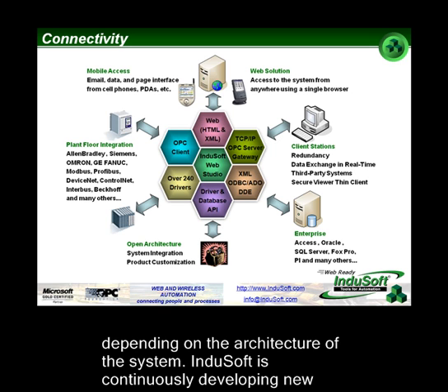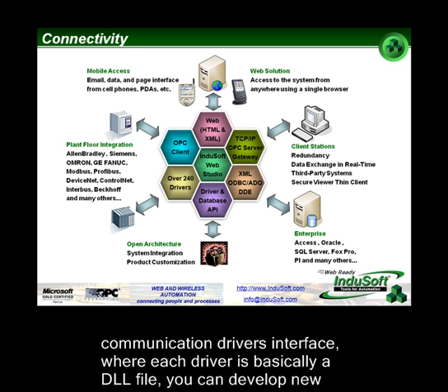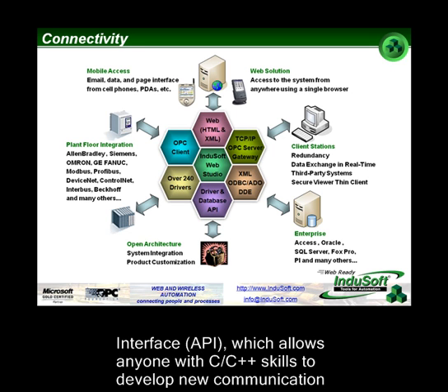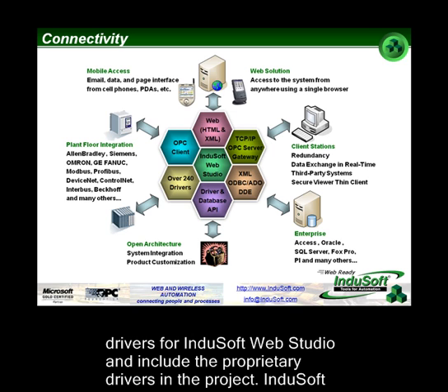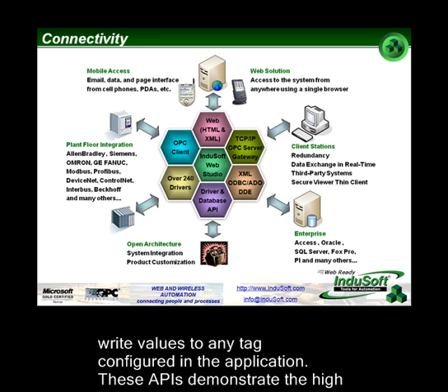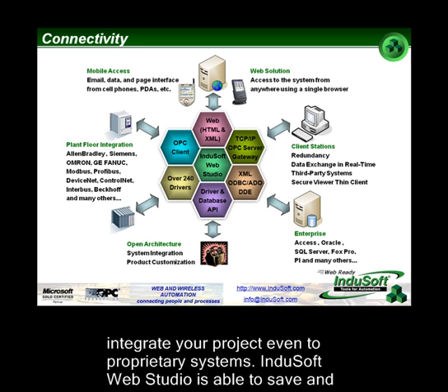InduSoft is continuously developing new communication drivers for emerging protocols. However, based on the modularity of the communication drivers interface — where each driver is basically a DLL file — you can develop new drivers yourself using the driver toolkit, an API that allows anyone with C or C++ skills to develop new communication drivers for InduSoft Web Studio. InduSoft also provides another API called the Tags Database Access Toolkit, which allows you to read or write values to any tag configured in the application. These APIs demonstrate the high level of openness of the InduSoft Web Studio architecture, allowing integration to proprietary systems.